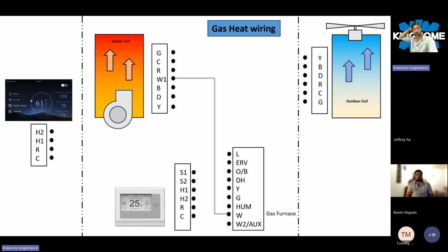One thing you have to focus on is that if you have a furnace installed, you need to power the W from this thermostat. From the thermostat inside the mechanical room, we're going to use W as the first stage of heat when using a gas furnace. If you have a 2-stage gas furnace, we can use W and W2. But if you have an air handler, it's a little different. We're going to use AUX as our first stage, to call for the electric heater to be powered on. This is the biggest difference in the wiring, so pay close attention and make sure to test it. If you have a call like no heat, make sure you have the right terminal connected to the system.